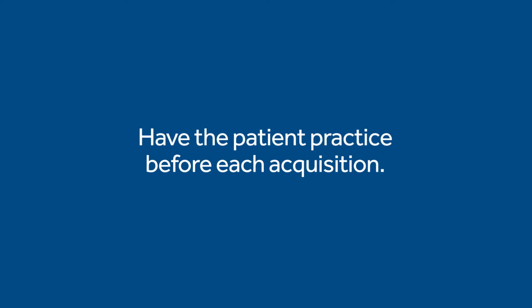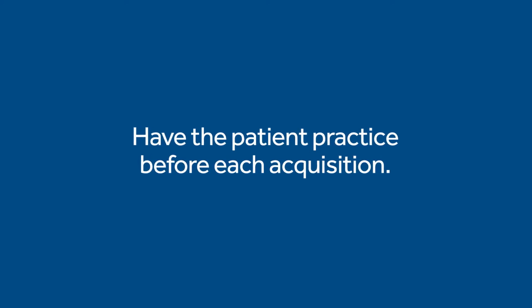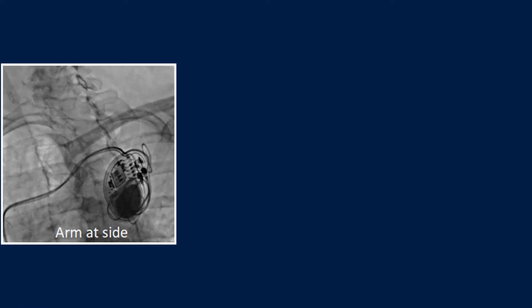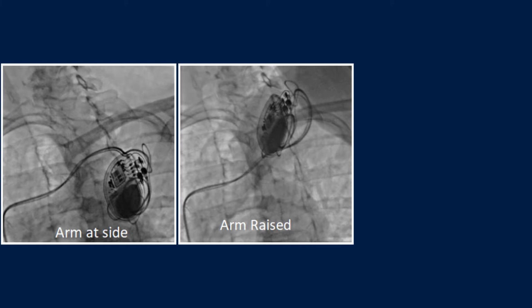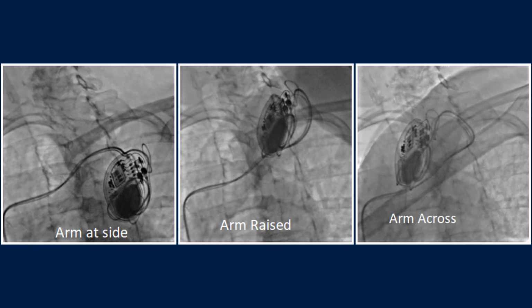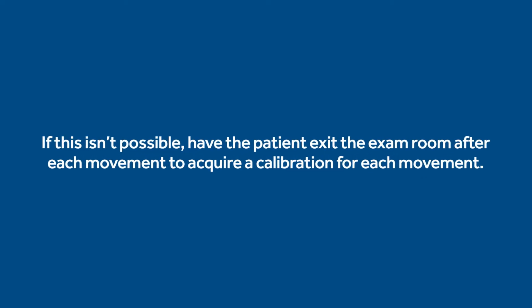Before each of the 2 arm movements, have the patient practice the arm movement. Provide clear instruction as they do it. Starting with the can at the lower right of the field of view, acquire a quick image at the beginning and end of both arm movements to ensure the device will not go outside of the field of view. Make adjustments to position as needed until you are able to fit both movements into the field of view. If at this point it is not possible to get both movements in the field of view, you will have to have the patient exit the exam room after each movement to acquire a calibration for each movement.